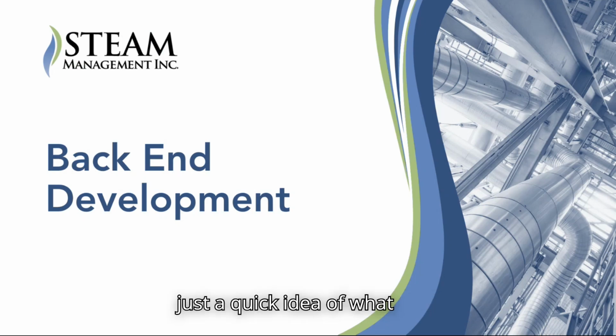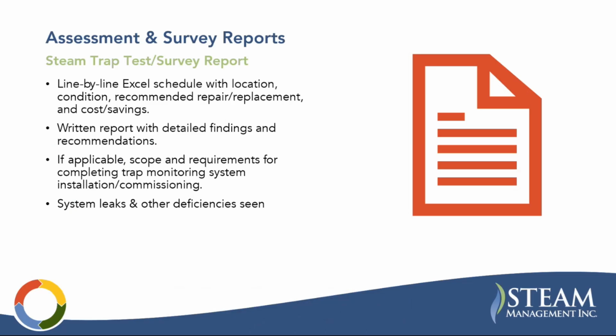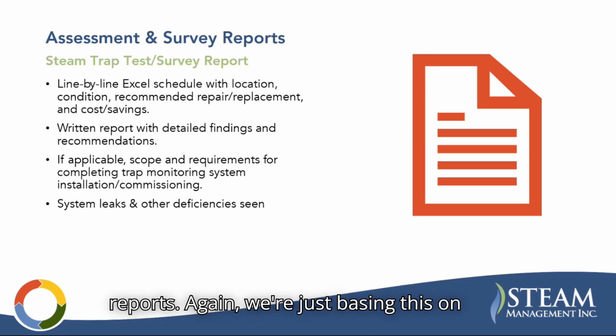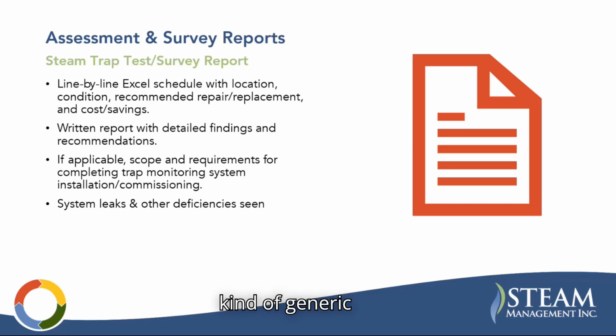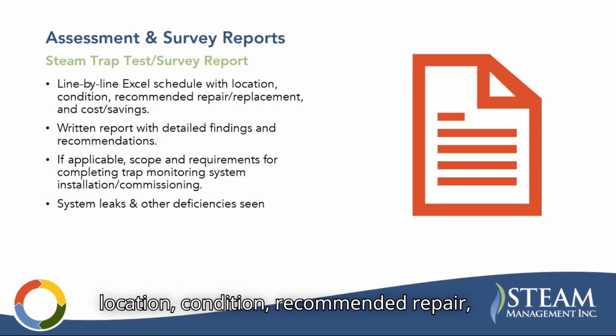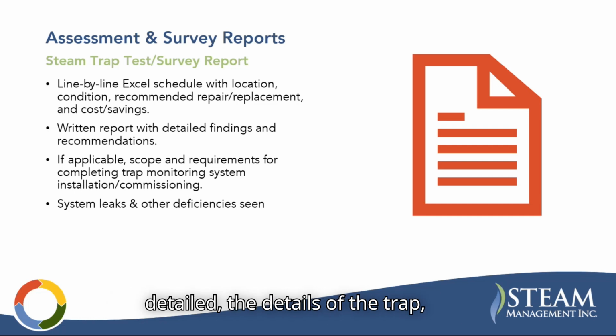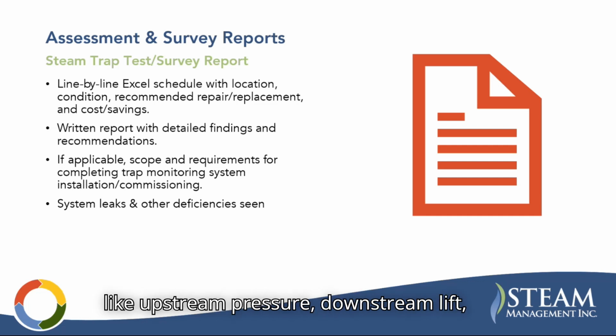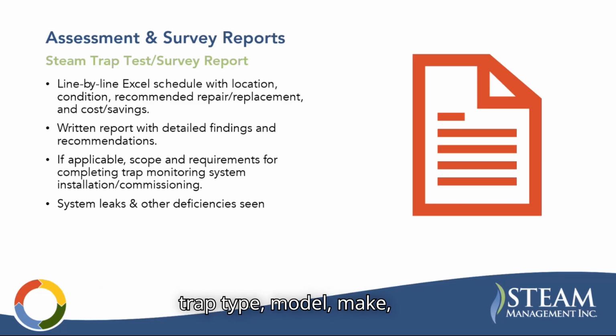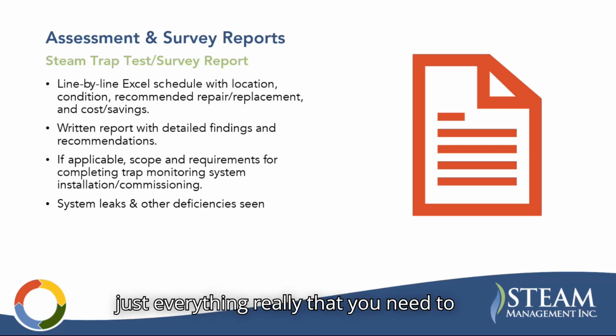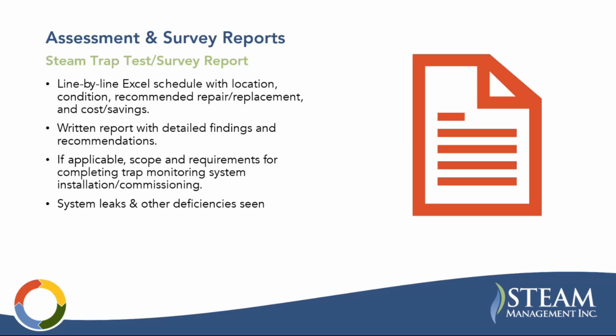Okay, so backend development, just a quick idea of what the expected deliverables are out of these reports. Again, we're just basing this on what we do, but I would think these are generic outputs that you would expect. For a steam trap test or survey report, we would provide a line-by-line Excel schedule with location, condition, recommended repair, replacement, cost savings, and also all the details of the trap, like upstream pressure, downstream lift, trap type, model, make, operating pressure, just everything you need to maintain and scope out a project for the failed traps as well.